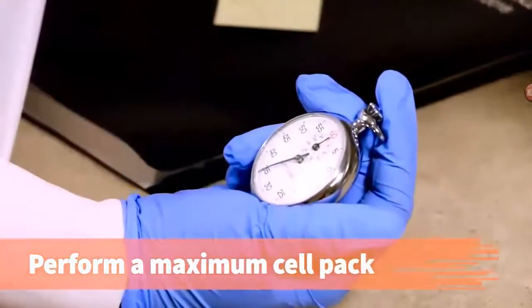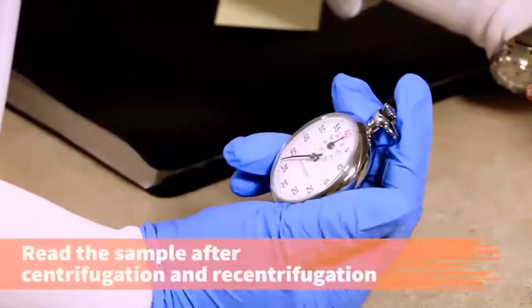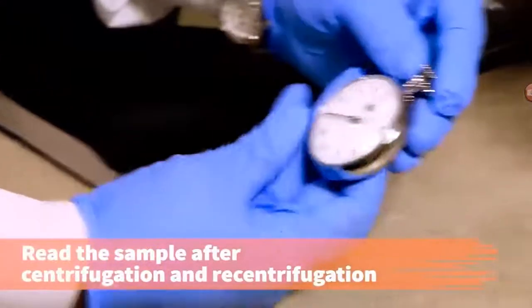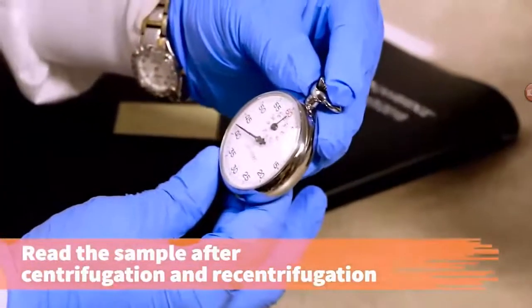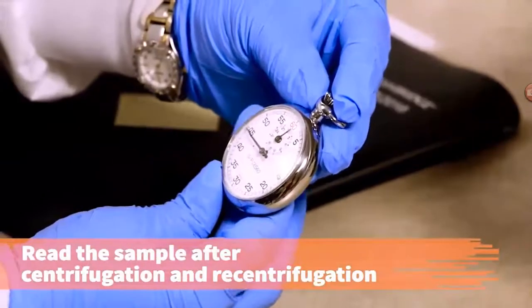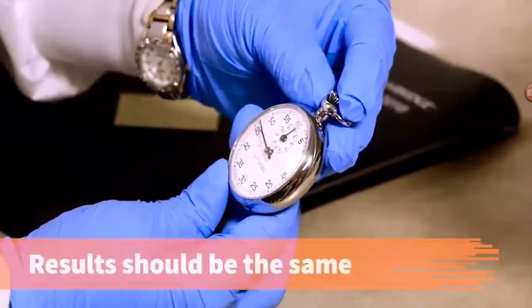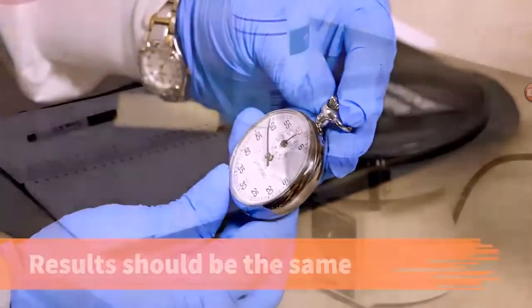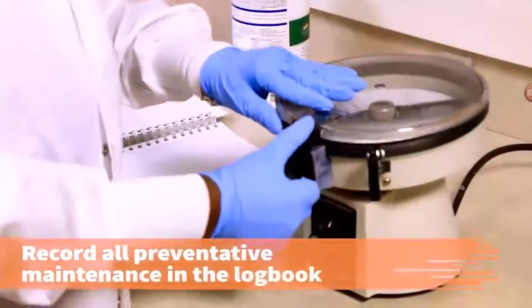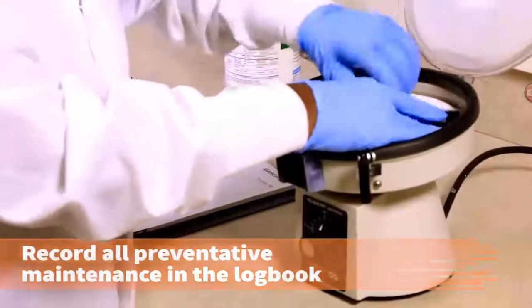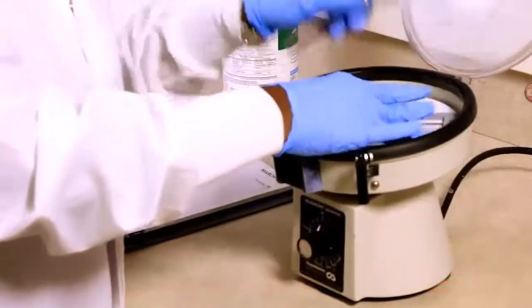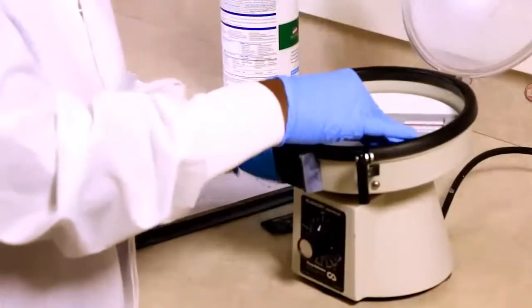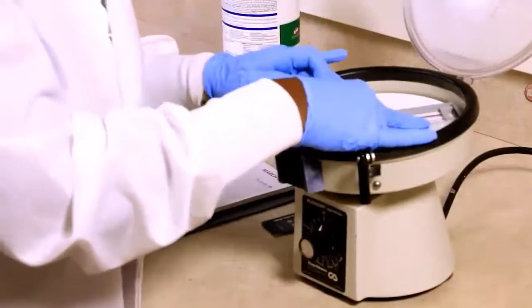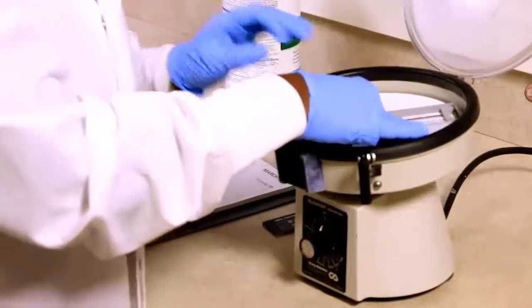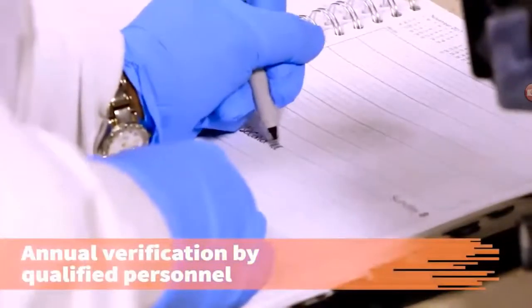Perform a maximum cell pack to verify the time required for complete packing by reading a sample after centrifugation and then recentrifuging for 1 minute. The results should be the same. If they are not, perform preventive maintenance or call the service technician. If the cells compact further during recentrifugation, the centrifuge is not rotating at the proper speed, and hematocrit results will be falsely elevated. Record all preventive maintenance in the laboratory logbook.